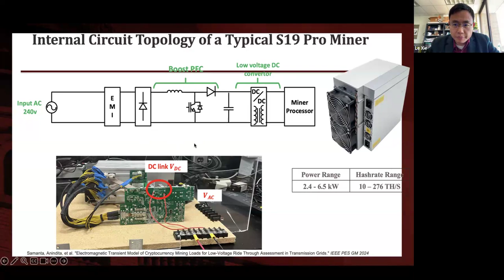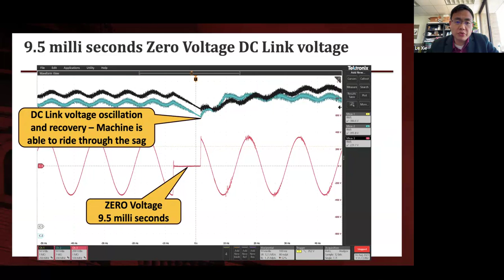We designed this low voltage or zero voltage ride-through test using the programmable AC source. We wanted to see, in a lab setting, how these computing loads respond to low voltage or zero voltage signals, given the different standards out there. Here's what we found: they were able to sustain up to about 9.5 milliseconds of close to zero voltage.